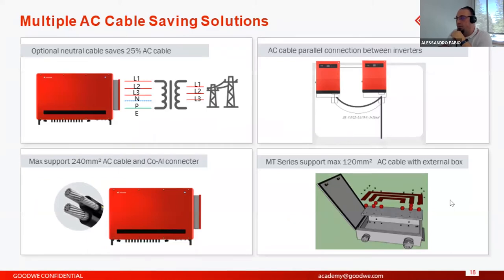For example, we have the multiple cable saving solution. We can connect the strings and the grid connection, even without neutral, because it's optional. The maximum supported AC cable for the connectors is 240 square millimeters, while the MT series supports max 120 square millimeters AC cable, with an external box, for example.